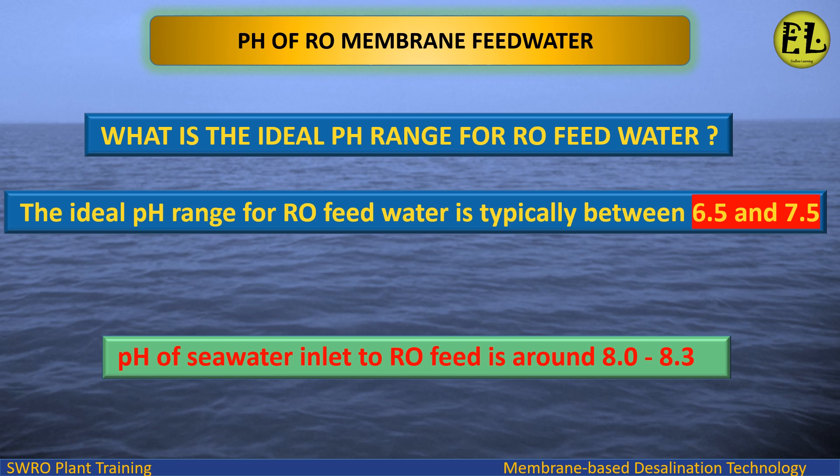The ideal pH range for RO feed water is typically between 6.5 and 7.5. The pH of seawater inlet to RO feed is around 8.0 to 8.3.